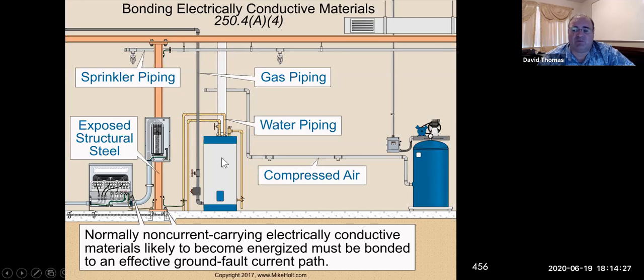But that one's kind of iffy, because some places with gas piping, like in San Francisco, don't want you to bond the gas pipe, but most other places do. Water pipe also will need to be bonded, and also any type of metal structure, metal buildings, metal I-beam. If you have a commercial industrial building, a lot of these are made out of metal beams, so we typically bond at one point on the beam for the building, closest to where the main service is. So in this case, what we did is, let me go into here.